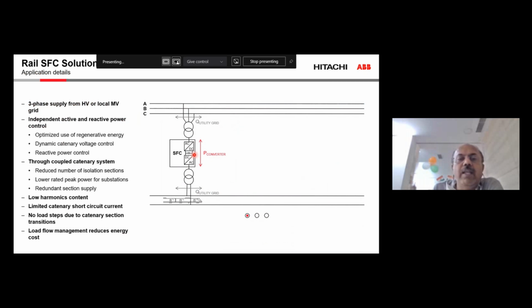At the same time, when we have a static frequency converter feeding to the railway network, say in this case two phases 25 kV and then the neutral, and it is drawing of course the power from all the three phases. So in that way we can control the real power flow from network to the railway feeding catenary, and also it independently compensates for the reactive power, not only at the network side, it is also compensating for the railway network. So in this sense, this static frequency converter can compensate the entire railway network, that is single phase railway network, for the reactive power, balance the voltage, and not only that, any excess energy due to the regeneration can be fed back to this network.